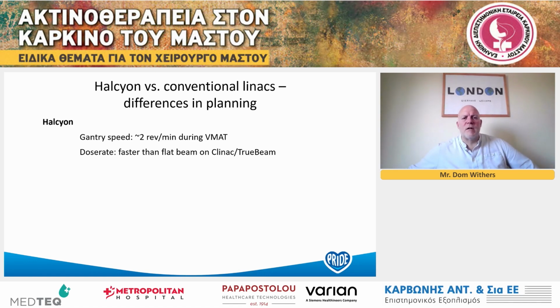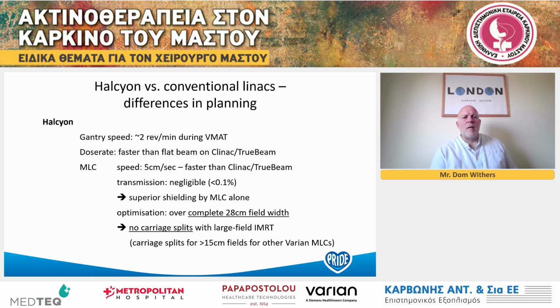The dose rate is faster than a flattened beam on a Clinac or TrueBeam or standard electron machine as well. It's 740 monitor units per minute rather than 600. The MLC is also faster than the Clinac and TrueBeam, and its transmission is very, very small. This means that when there is only MLC in the field, there is superior shielding compared with those MLCs. And this is important for the doses that your organs at risk are getting. It means that your dose is more concentrated to the target and better shielded to your organs at risk when you're optimizing. Also, during optimization, those leaves can travel over the complete 28 centimeter width of the field.